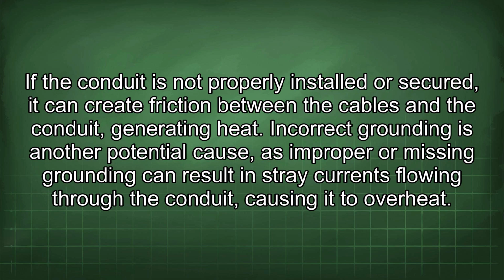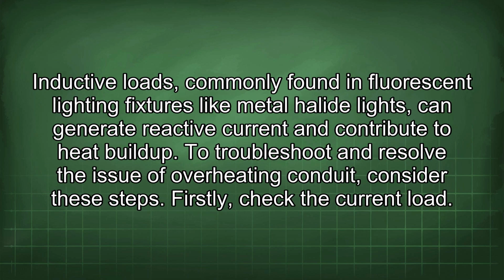heat. Incorrect grounding is another potential cause, as improper or missing grounding can result in stray currents flowing through the conduit, causing it to overheat. Inductive loads, commonly found in fluorescent lighting fixtures like metal halide lights, can generate reactive current and contribute to heat buildup. To troubleshoot and resolve the issue of overheating conduit, consider these steps.